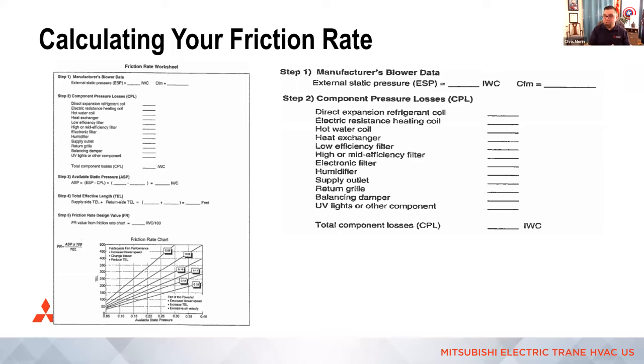And the component pressure losses are actually based on the volume of air you're putting through it. So if you have a big air filter that's 4 or 5 inches pleated, you might have a much lower pressure loss when you put, let's say, 300 CFM through it compared to when you put 600 CFM through it. So the pressure loss would go up with more volume of air.